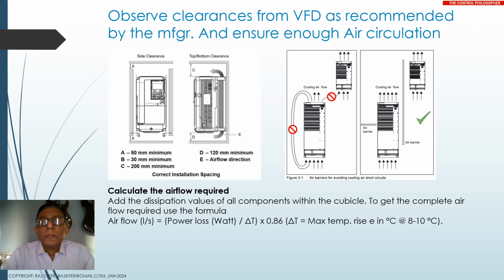All right, and on the diagram on the left, which is for a Siemens VFD, he says that you cannot mount the VFDs below one another, and he even says do not install them without a partition. This is because the partition or air barrier, which is shown in the diagram, is to guide the airflow of each drive separately.